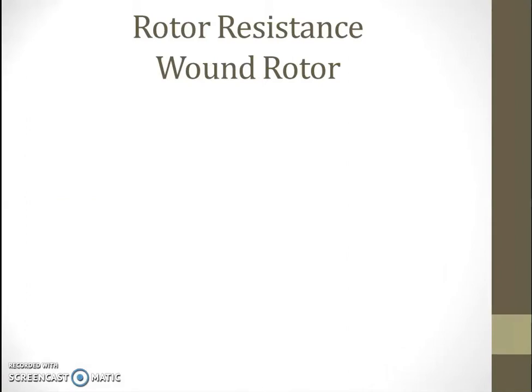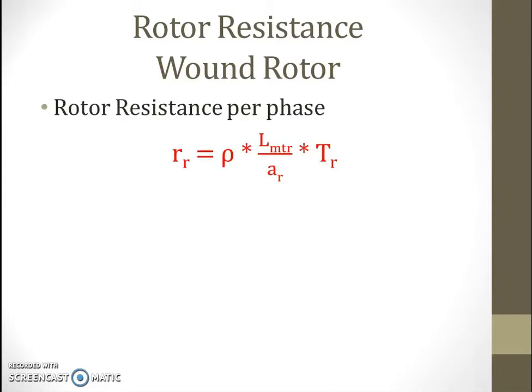Now, rotor resistance of wound rotor. As I said stator resistance remains common, so now we look at rotor resistance. First we see how to calculate rotor resistance for wound rotor. Rotor resistance per phase is given by a similar equation — suffix R is for rotor — so it is rho multiplied by length divided by cross sectional area and multiplied by total number of rotor turns per phase.